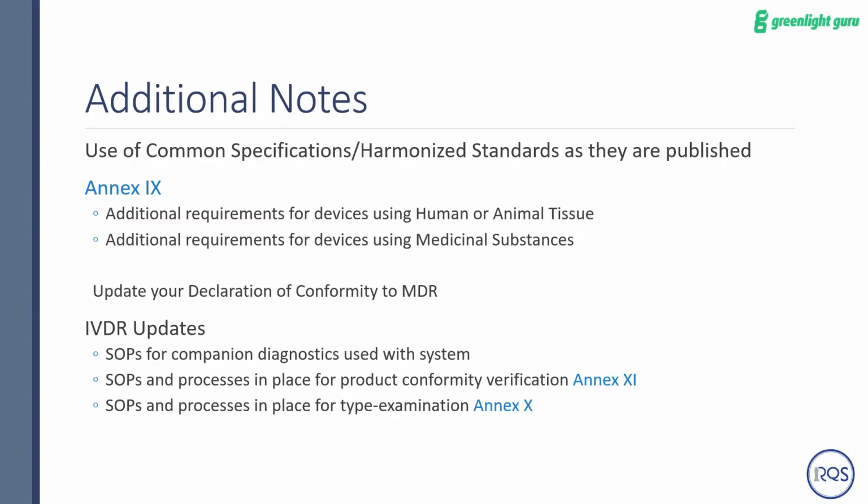So that will be a new procedure as well, outlining how you plan to review for common specifications when they get created and if they affect your device, as well as making sure that you comply with those. And that's tied a little bit to the clinical evidence and getting new devices on the market. You could also show that they meet the common specifications, but it's not very well defined at this point.